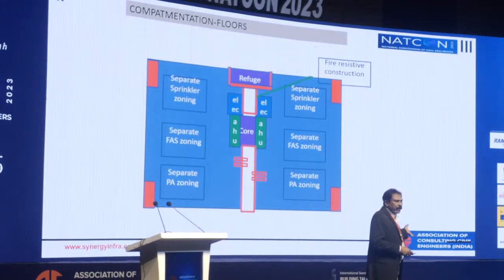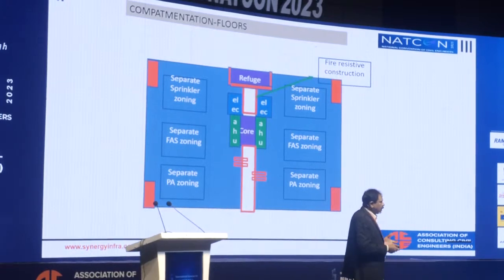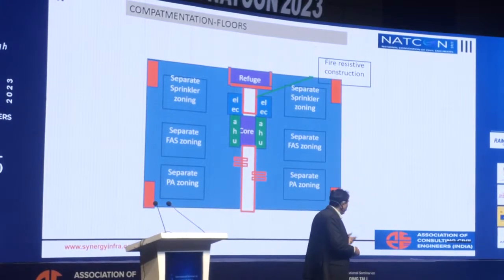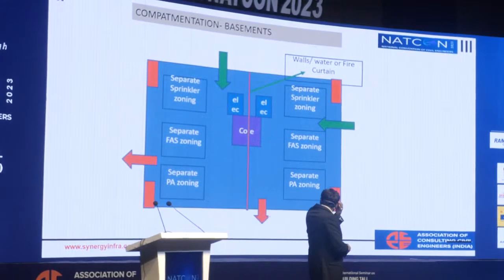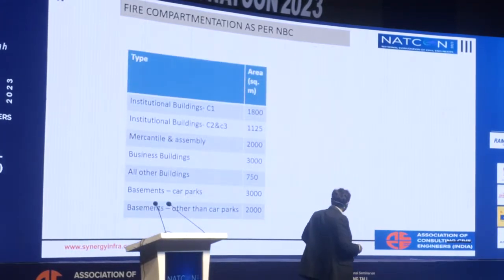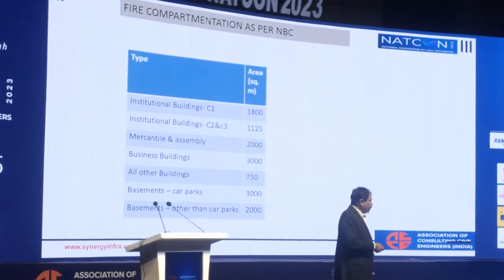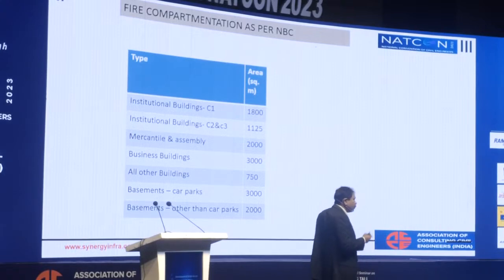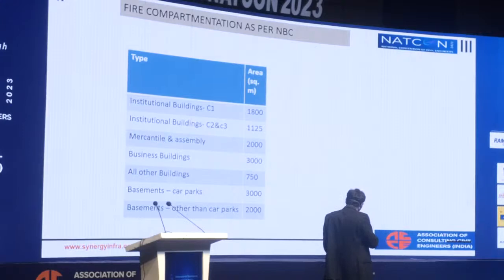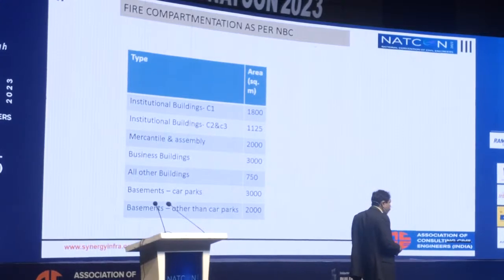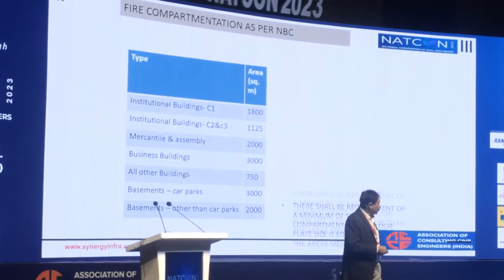Or otherwise, we need to have fire dampers or fire sealants across the zones where services pass through. And this is for the basements. These are the fire compartmentations as per NBC. In the morning Dr. Suresh talked about the basement. So every 1800 square meters for hospitals, 1125 square meters for institutional buildings, and where basements are used as car parks, then it is around 3000 square meters.